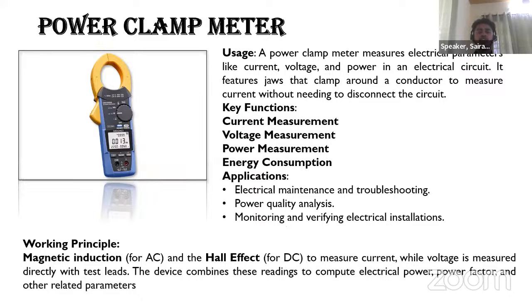Coming to the power clamp meter, for assessing the motors and capacitor banks, these power clamp meters play a major role. With the help of this power clamp meter, without disturbing the working condition of the equipment, we can measure the current, voltage, power, and energy. With these measurements, we can directly compare with the rated power, current, or voltage of the motor, and come to a conclusion on whether there is any issue with the operating conditions of the motors or any devices. Then we can start the troubleshooting.